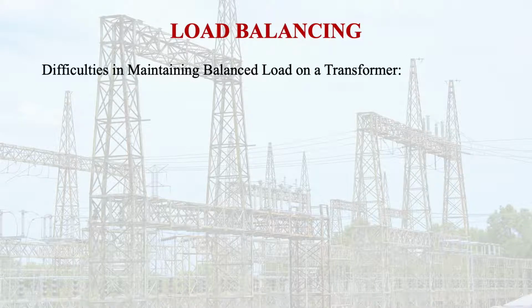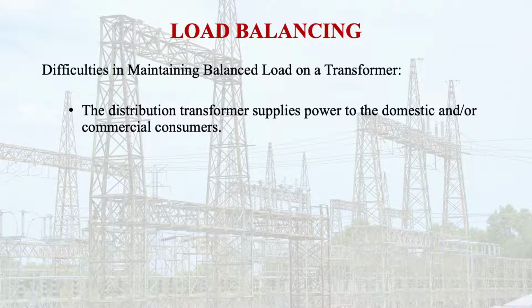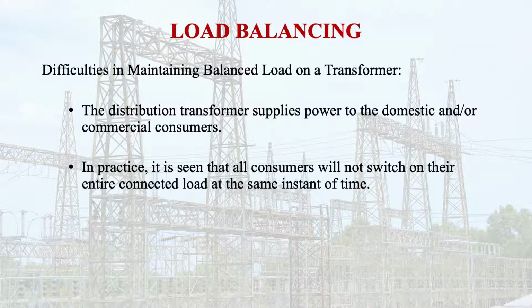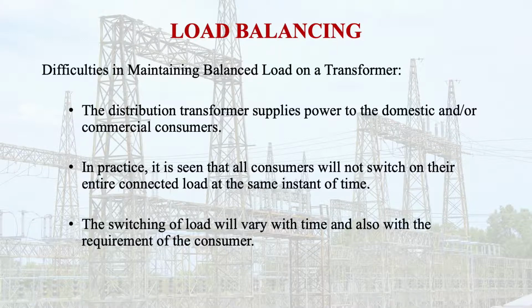So, difficulties in maintaining the balanced load on a transformer. So what are these? Let us discuss briefly about this. The distribution transformer supplies power to domestic and commercial consumers. In practice, it is seen that all the consumers will not switch on their entire connected load at the same instant of time, which are connected to the distribution transformer three phases. So switching of load varies with time, and also with the requirement of the consumers.